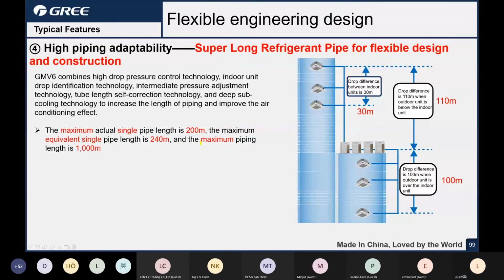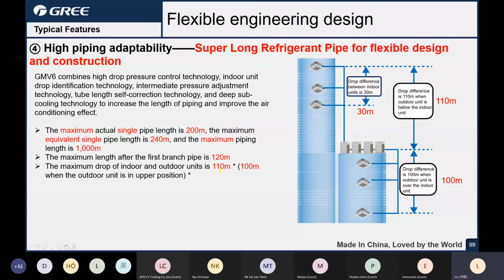And the total pipe length is 1,000 meters. And the maximum length from the first branch to the farthest indoor unit is 120 meters. And the height drop is 110. For indoor units, 30 meters. Okay, and you can see a lot of specification limits are improved compared with the GMV5. That means the adaptability for the project and the design is better for GMV6.